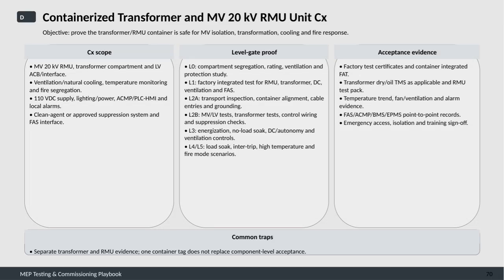This slide focuses on the testing and commissioning of containerized transformers and medium voltage 20 kV ring main units, or RMUs. The objective here is to ensure that the transformer and RMU container is safe for medium voltage isolation, transformation, cooling, and fire response. First, let's look at the commissioning scope.